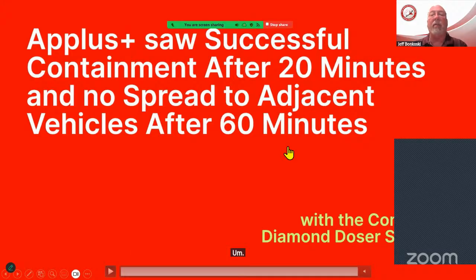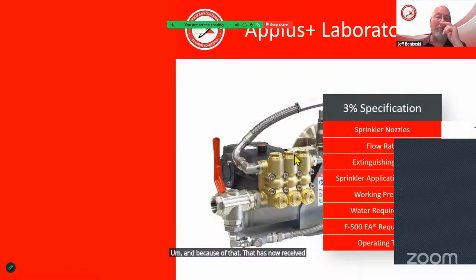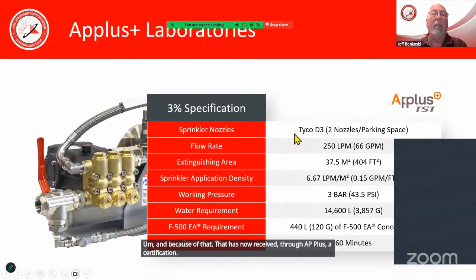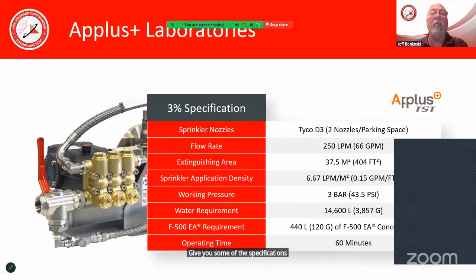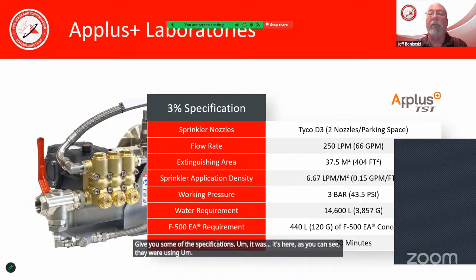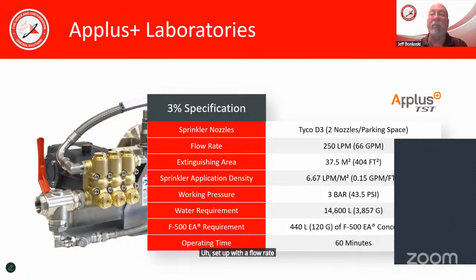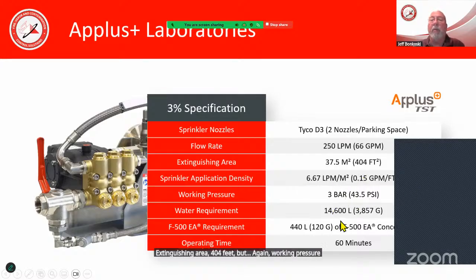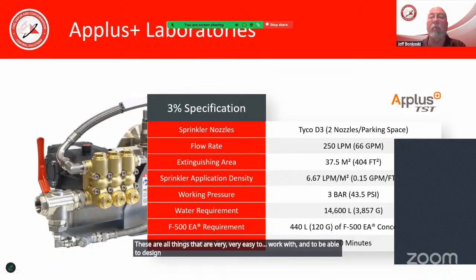Because of that, it has now received certification through Applus+. To give you some specifications, they were using Tyco D3 nozzles, with a flow rate of basically 66 gallons per minute, an extinguishing area of 404 feet, and a certain working pressure. These are all things that are very easy to work with and to design with us.